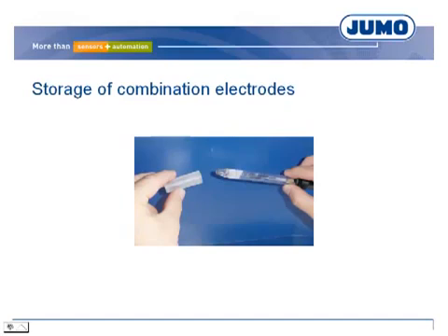The storage time of combination electrodes is limited and it is recommended to use them within six months. The electrodes are stored in a wet-retention cap filled with KCl solution to protect against drying. Otherwise, the electrolyte of the reference system seeps out and cracks can open the membrane.